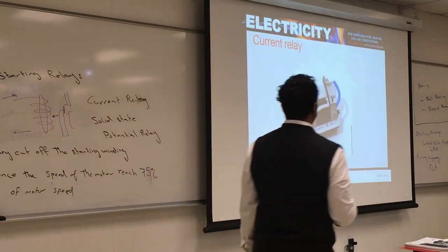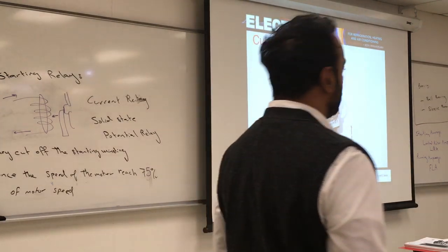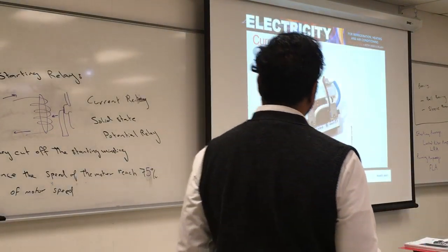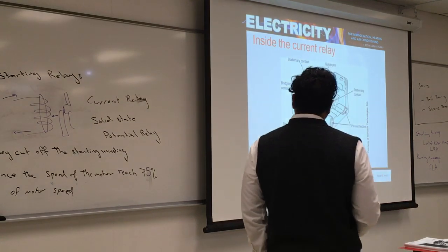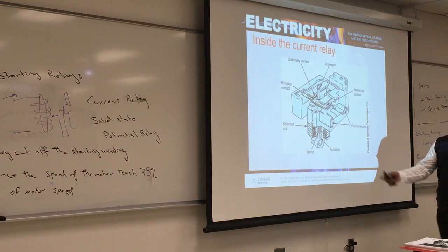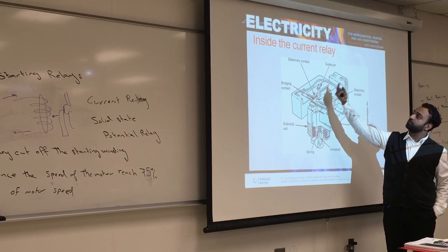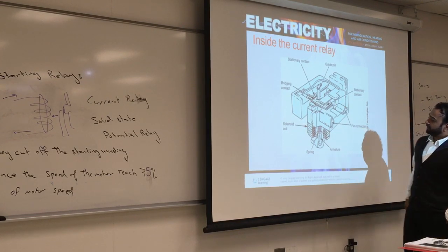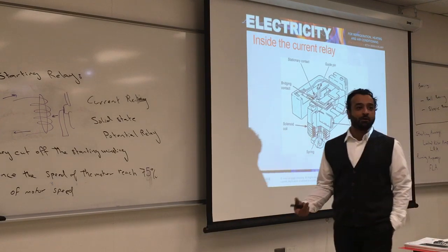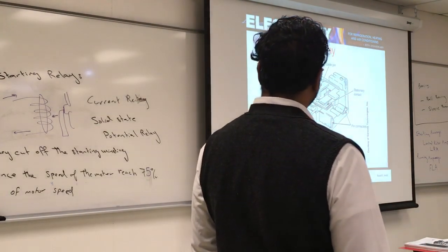This is what it looks like. This is the current relay. And you see the coil here. These are my leads. And the coil will push in or close a pin in here. And this is how it's plugged in. And you see the coil inside. There's a pin inside to push things in and out. This is the current relay. And the problem you will see them outside the hermetic compressor. Is the bearing inside the relay? There's no bearing in the relay. Just a pin. Push in and out and make a contact or not. This one's the inside. See the pin? This is the pin. And this is the coil. Similar to here. This is your coil. This is your pin. Once it's energized, it goes up. It goes down based on the polarity in here. And there's a spring to keep it in place.